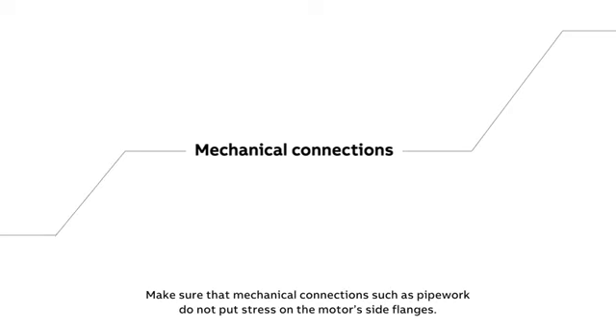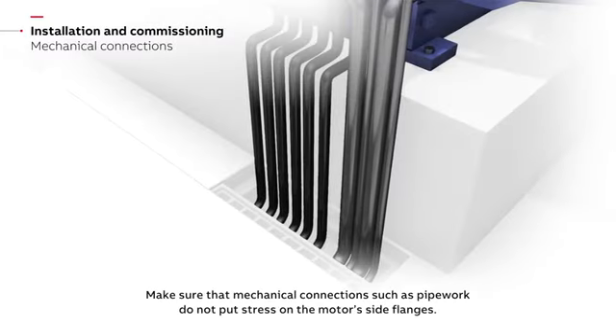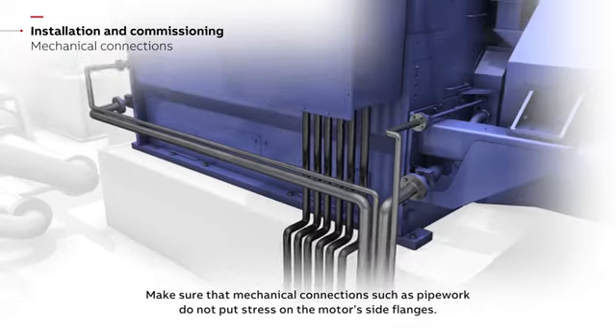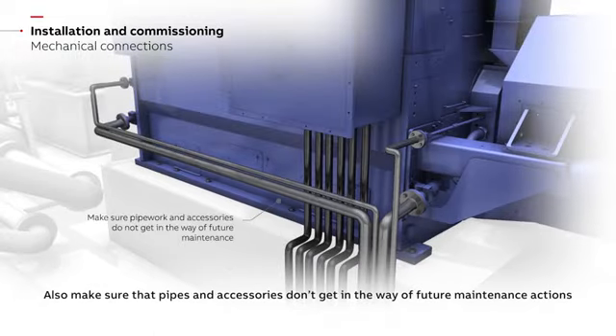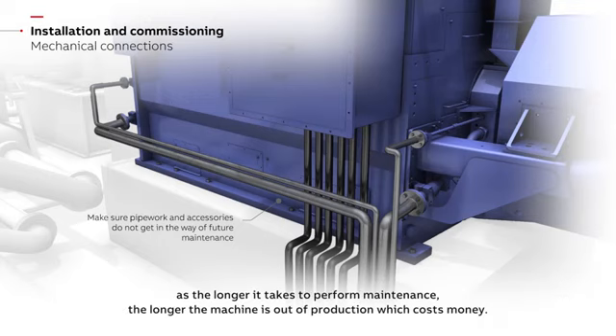Make sure that mechanical connections such as pipework do not put stress on the motor's side flanges. Also make sure that pipes and accessories don't get in the way of future maintenance actions, as the longer it takes to perform maintenance, the longer the machine is out of production, which costs money.